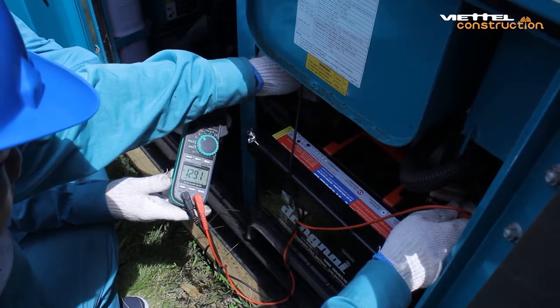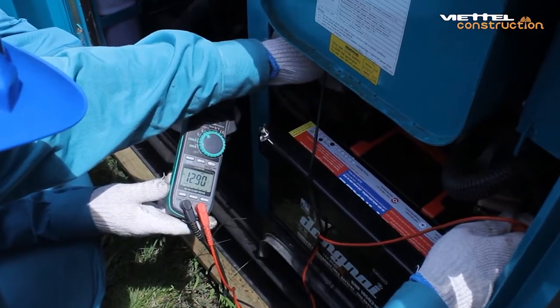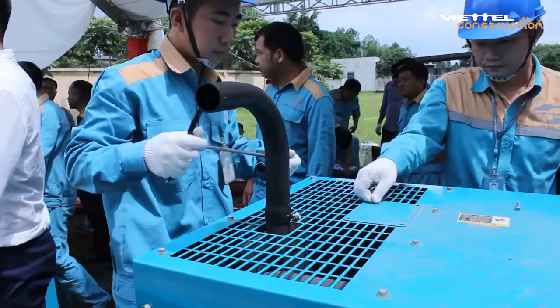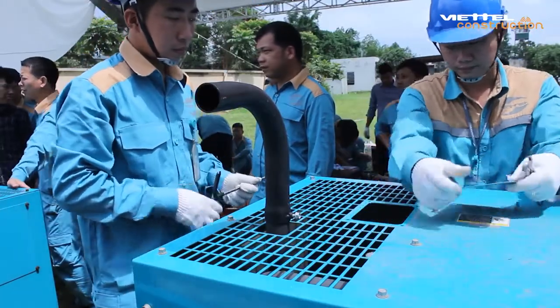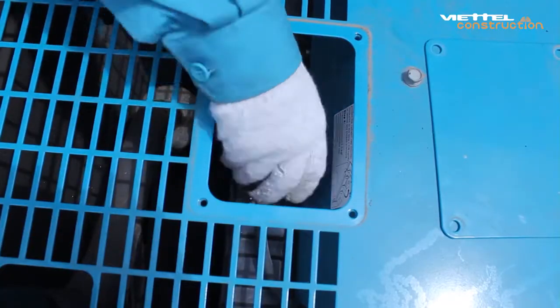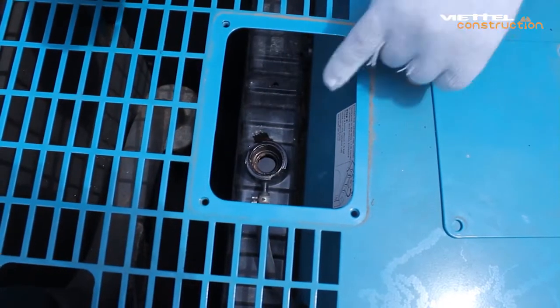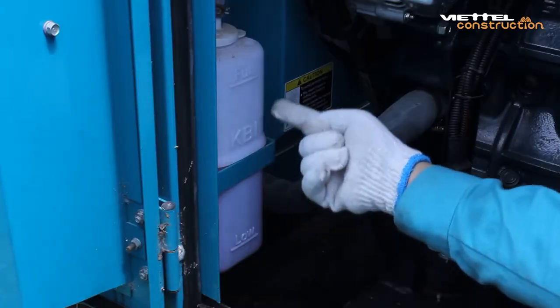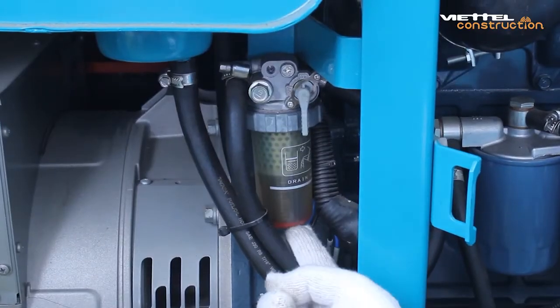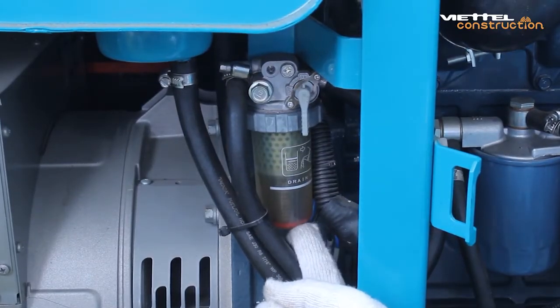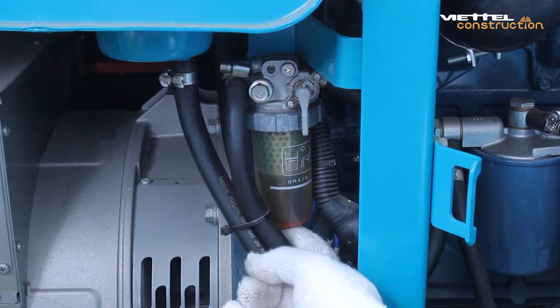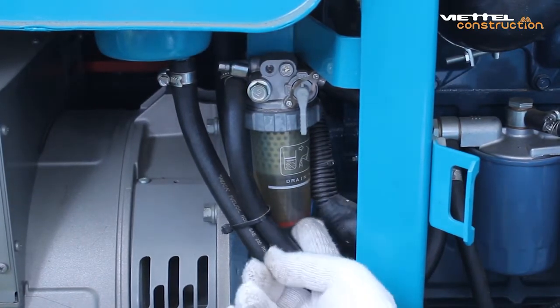Use the meter to measure the output voltage of the battery. Greater than 12 VDC is reached. Open the lid. Check the cooling water in the radiator and in the container. Check the filter water separator. If the red rubber pushes too high, which means the oil tank has a lot of water, it is necessary to discharge the entire oil tank.